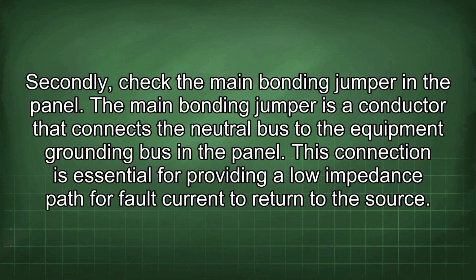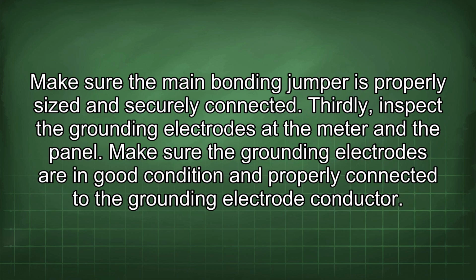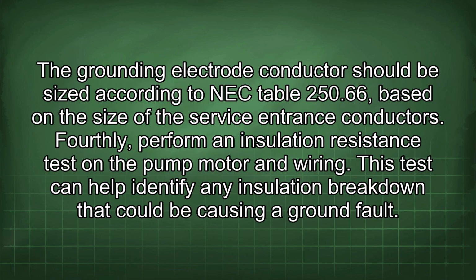Secondly, check the main bonding jumper in the panel. The main bonding jumper is a conductor that connects the neutral bus to the equipment grounding bus in the panel. This connection is essential for providing a low impedance path for fault current to return to the source. Make sure the main bonding jumper is properly sized and securely connected. Thirdly, inspect the grounding electrodes at the meter and the panel. Make sure the grounding electrodes are in good condition and properly connected to the grounding electrode conductor. The grounding electrode conductor should be sized according to NEC Table 250.66 based on the size of the service entrance conductors.